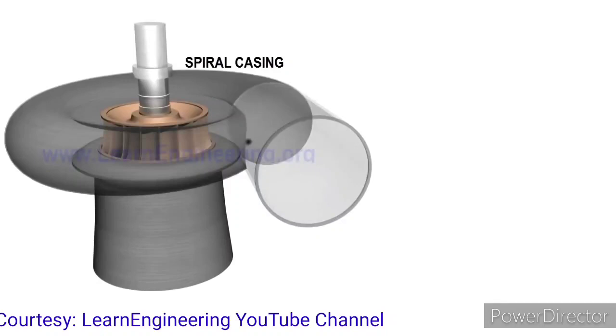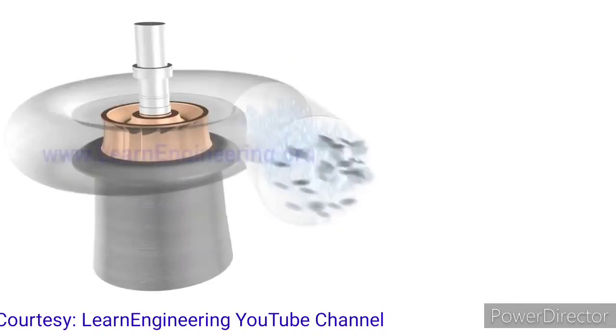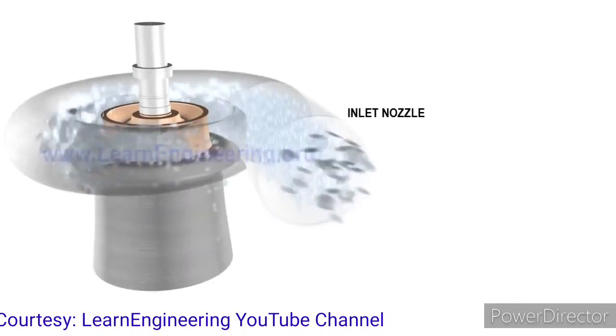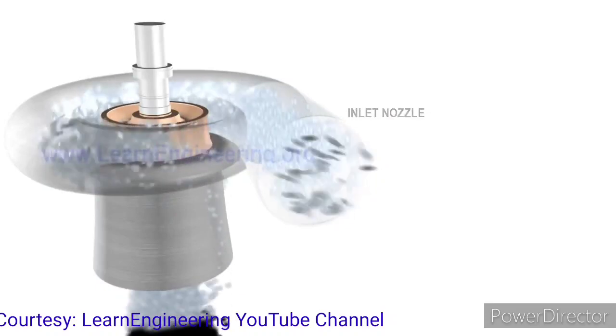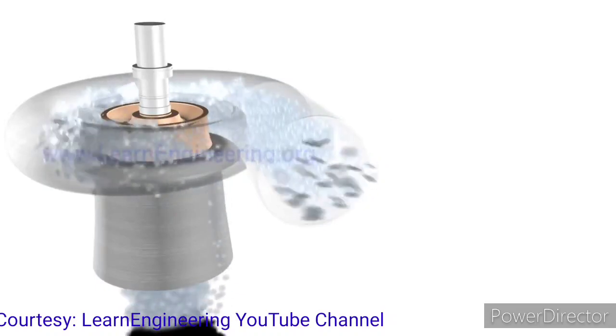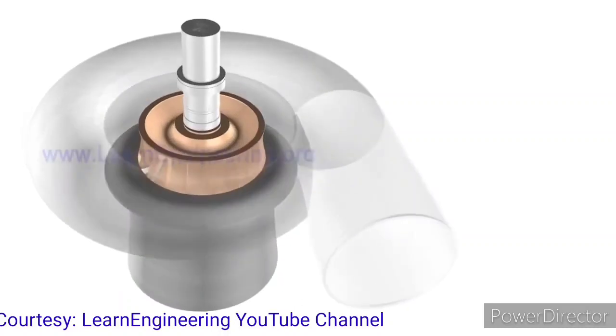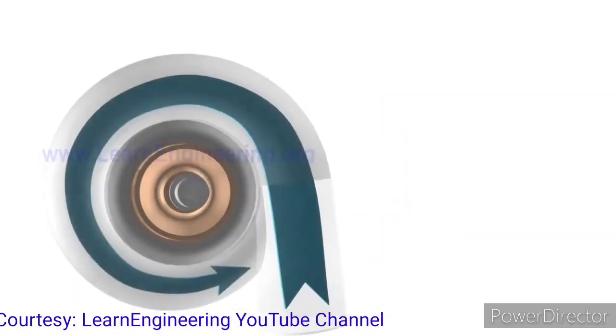Flow enters via an inlet nozzle. The flow rate of water will get reduced along the length of the casing, since water is drawn into the runner. But the decreasing area of the spiral casing will make sure that flow enters the runner region at almost uniform velocity.